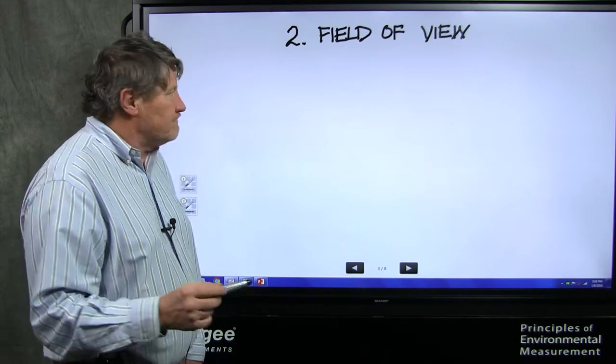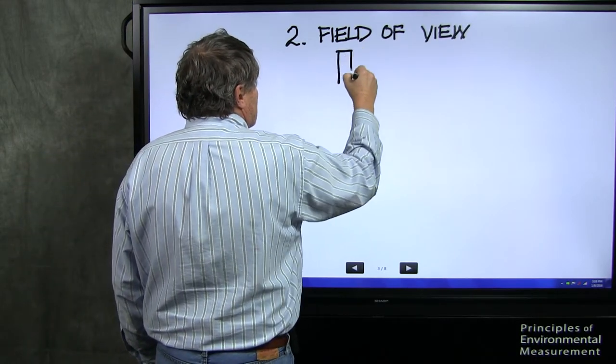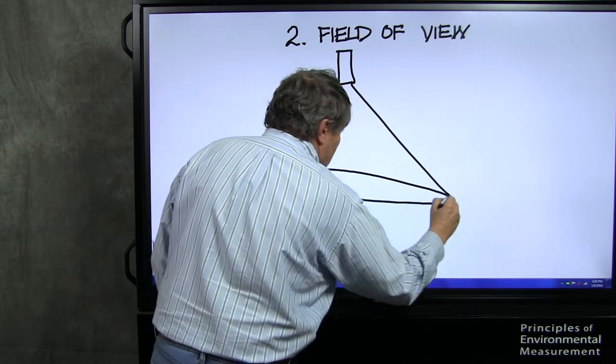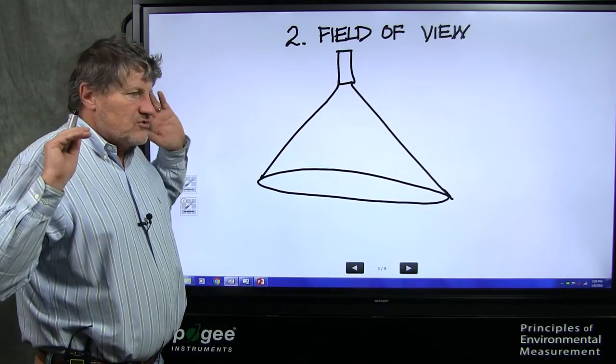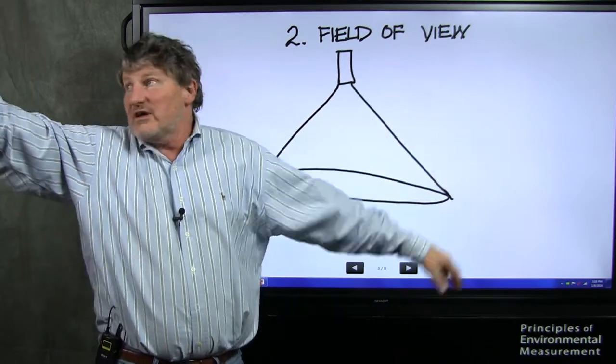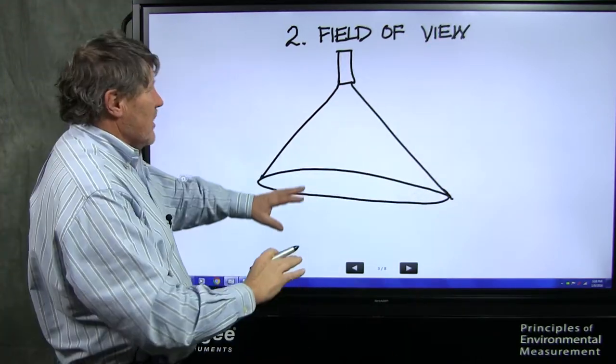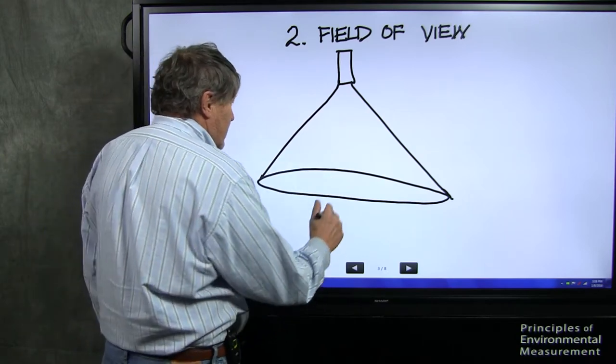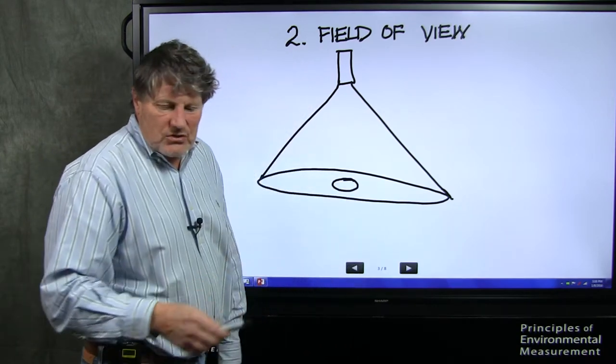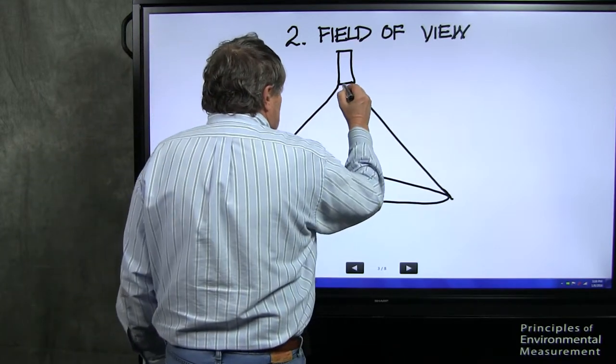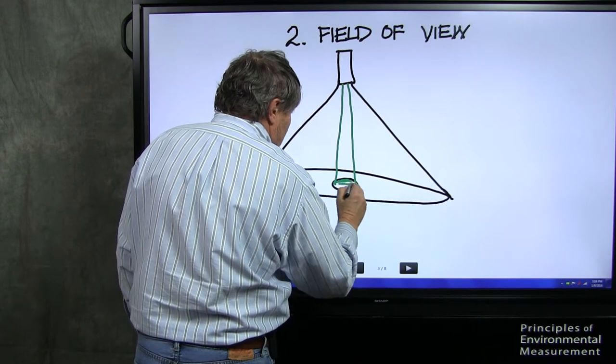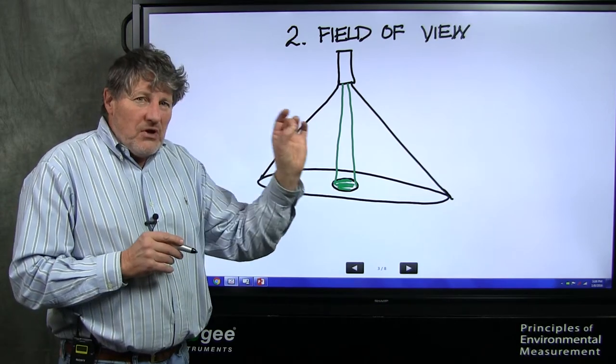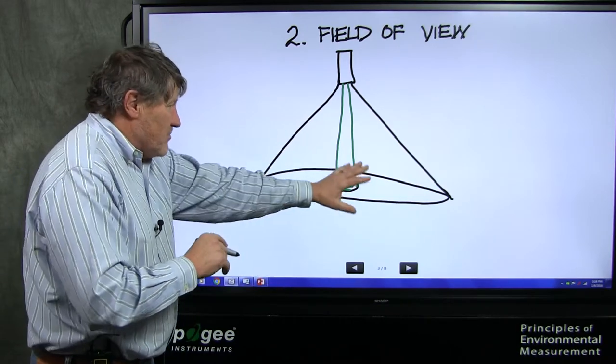Number two, field of view. All of these sensors, if we put a sensor right here, have a cone-shaped field of view. A low cost sensor has an enormous field of view. It sees the edges, it sees the sky, it sees the ground, it averages everything. If you really wanted to average everything, that'd be fine. But typically, what you really want to see is a small area in there. So the Apogee sensors have variable fields of view, but they're typically much tinier, depending on the type of sensor. So you can pinpoint the temperature of a spot rather than average a big area.